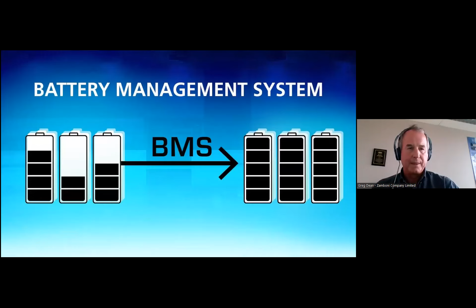What does the BMS do? Within the battery pack itself, we have multiple modules. It could be 4, 6, or 8, depending on the battery size. The BMS is the smart part of the system that, as the batteries discharge, they may become unbalanced—one may discharge more than the other. The BMS itself ensures that the batteries maintain balance and equal charge, which helps with maintaining a longer life and ensuring the batteries are there when you need them.